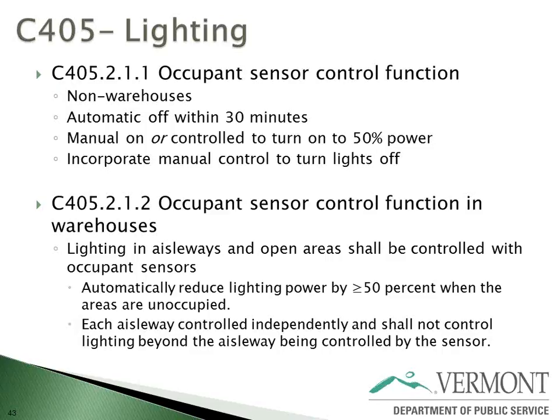Now we get into warehouses, which Stephanie deals with a lot. I don't think this is anything beyond good lighting design for a warehouse. You have aisleways in a lot of warehouses—light the aisleways, control them independently, don't control beyond the aisleways, and reduce lighting power by at least 50% when unoccupied. In most warehouses the lights actually go out; only when you move to each section does it turn on a couple of sections ahead. They don't reduce the light, they literally shut it off.